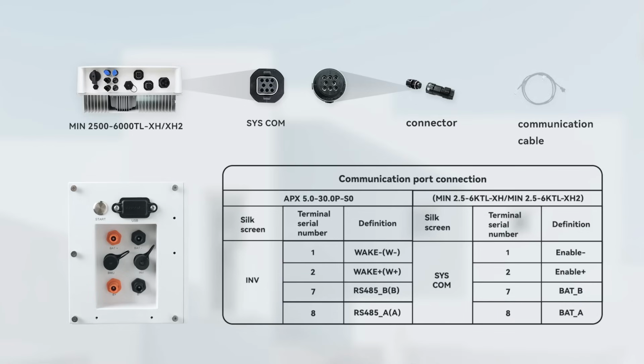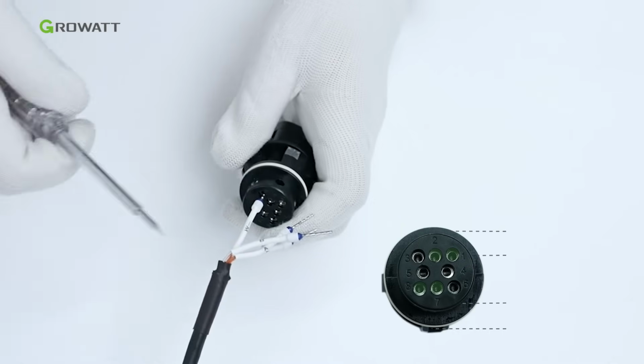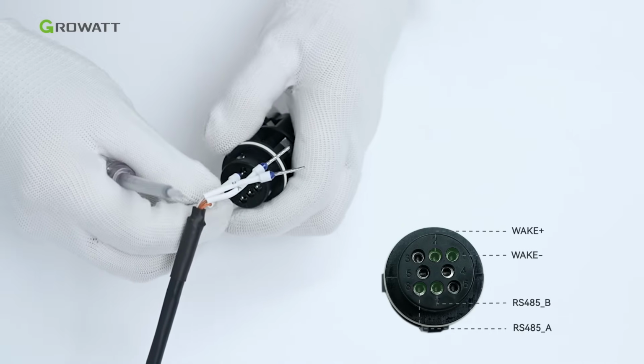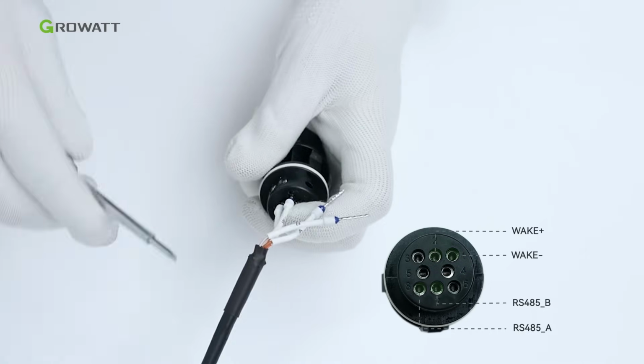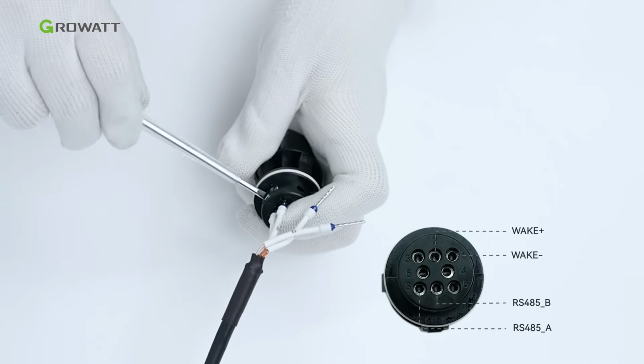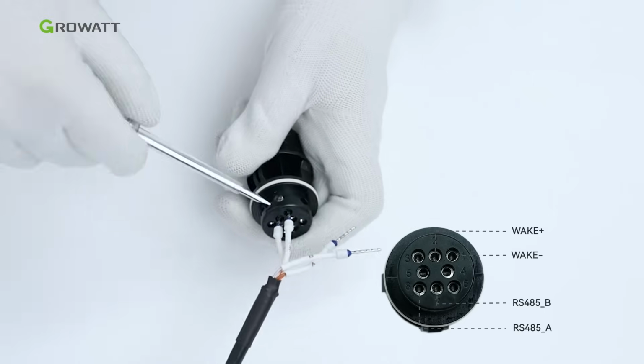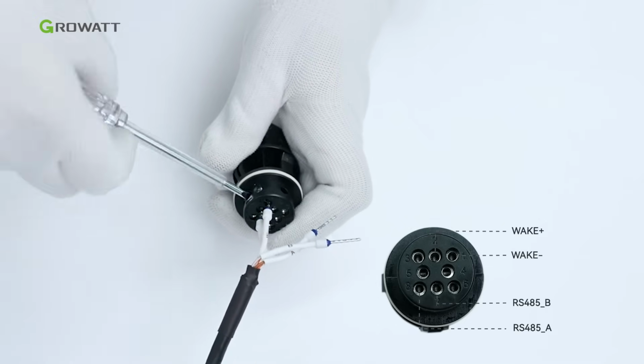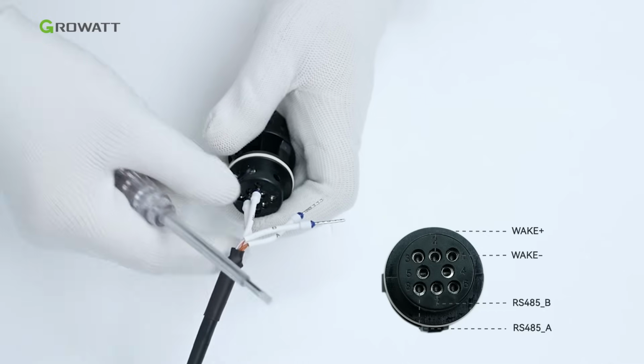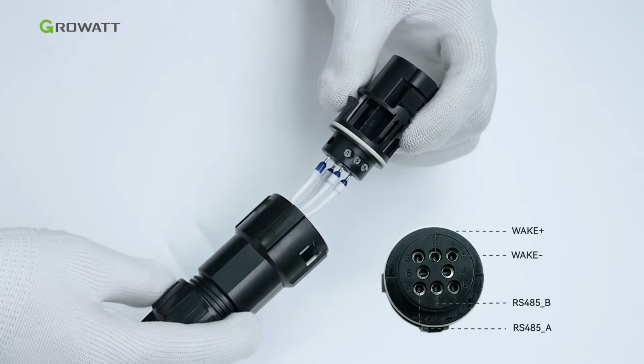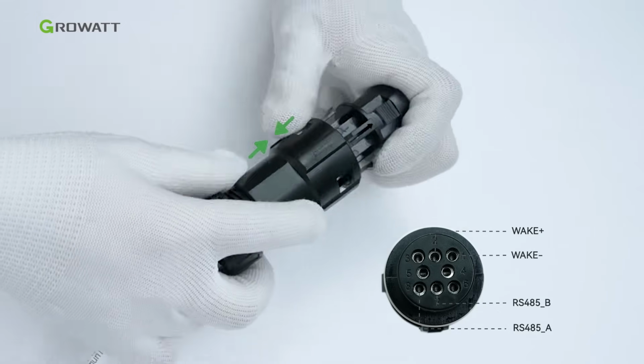Communication cable is used for communication between the power module and the inverter. The terminal definitions for the connector are shown in the table. Select the terminals 1, 2, 7, and 8 on one end of the communication cable and insert them into ports 1, 2, 7, and 8 of the connector. Lock the side screws to secure the pins. Lock the communication connector according to the position of the arrow.